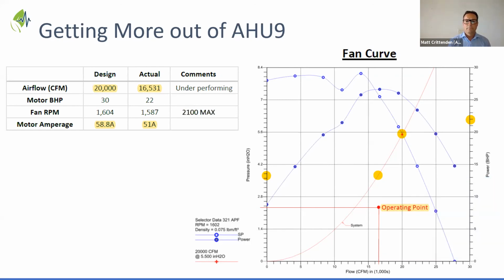So it would be nice to get in and see that fan close up. Right now, this is dynamic testing. The fan's running, so we can take everything from the outside. It would be nice to get into the fan unit, stick a hose right in the fan wheel, and then run a hose outside to the outer cabinet to get a much more accurate static pressure.